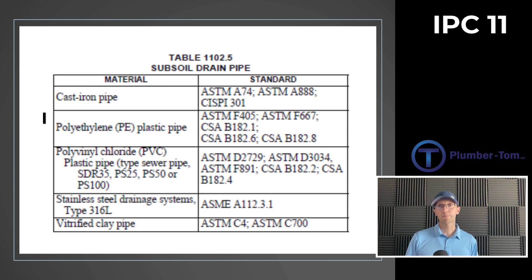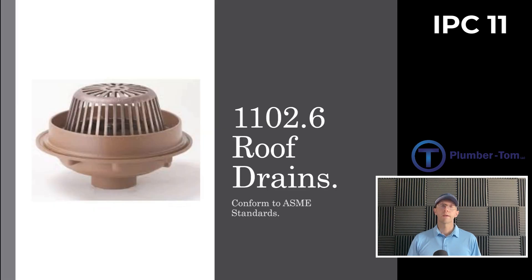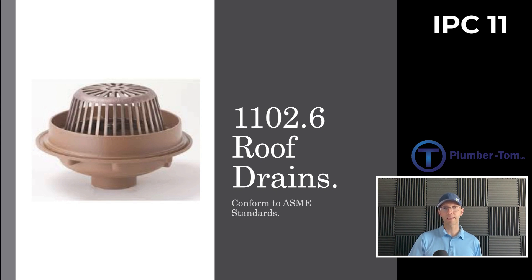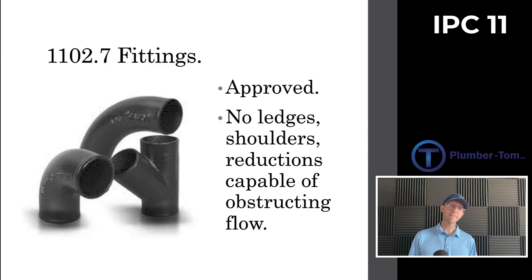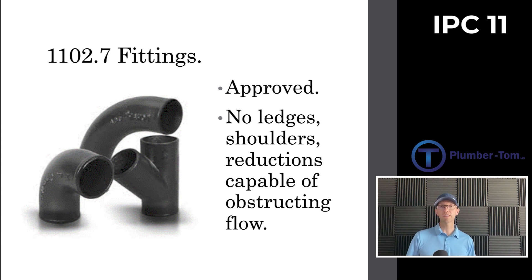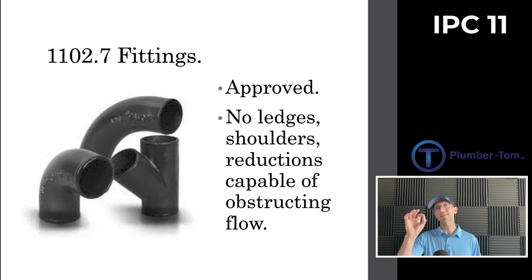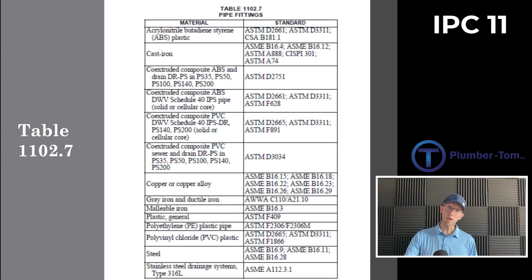Table 1102.5 gives us specific materials that can be used for subsoil drains. 1102.6 talks about the roof drains themselves — the bowl-shaped drains installed on the roof. These assemblies have to meet certain ASME standards, which is basically what that section covers. 1102.7 talks about fittings. Fittings have to be approved just like in Chapter 7, with no ledges, shoulders, or reductions capable of obstructing flow. With cast iron fittings, look them over for tar globs or manufacturing defects, and check for pinhole leaks — it's always less fun to find those after the system is full of water.